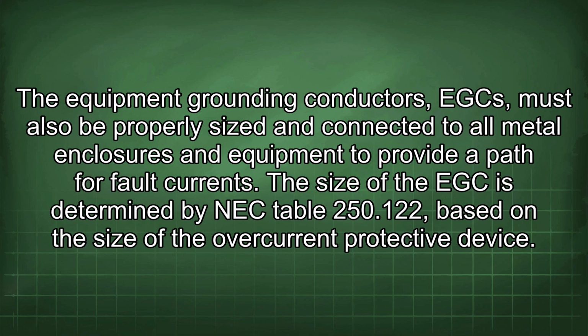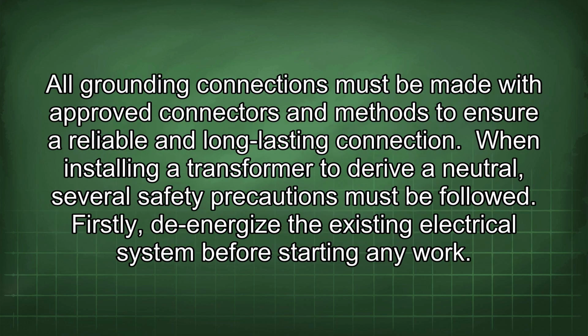The equipment grounding conductors, EGCs, must also be properly sized and connected to all metal enclosures and equipment to provide a path for fault currents. The size of the EGC is determined by NEC Table 250.122 based on the size of the overcurrent protective device. All grounding connections must be made with approved connectors and methods to ensure a reliable and long-lasting connection.